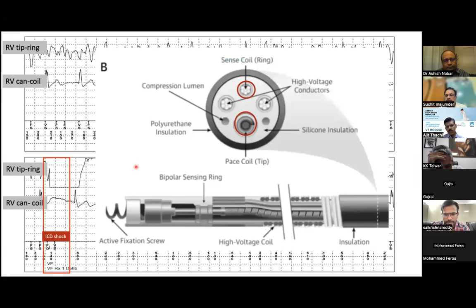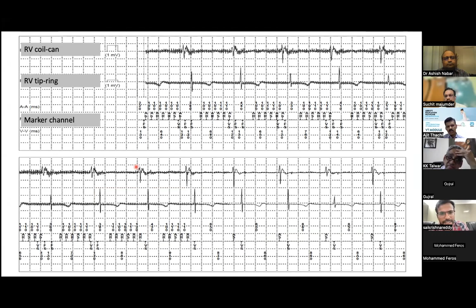Okay. In that EMI case, where the EMI was picked up only in the atrial lead and the ventricular lead was not showing any signals, what is the reason? Is it the autogain settings or something? It could be because of two or three reasons, sir. One, the sensitivity and the decay in sensitivity are different for the atrial channel and the ventricular channel. And the other thing is the filter settings are also different for the ventricular and atrial channels. Probably those were the reasons why the ventricular channel did not sense the signals.